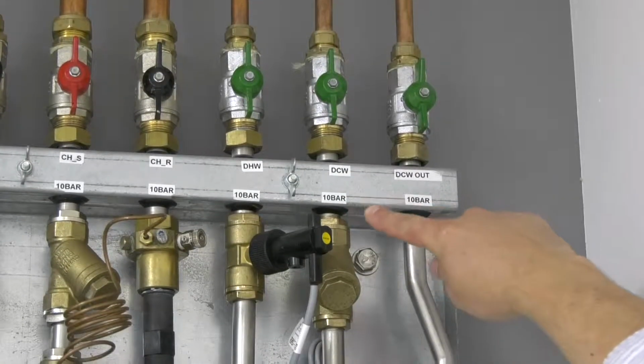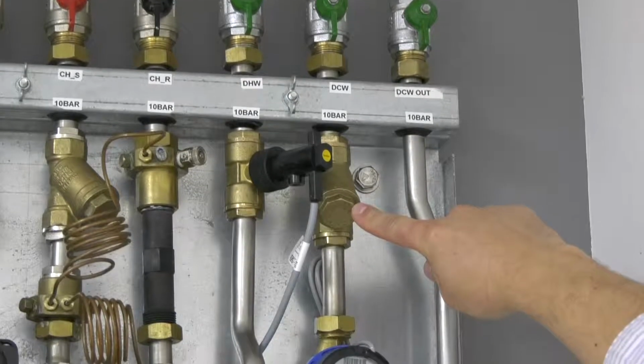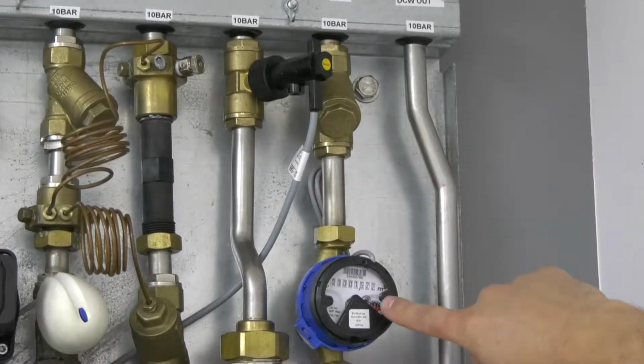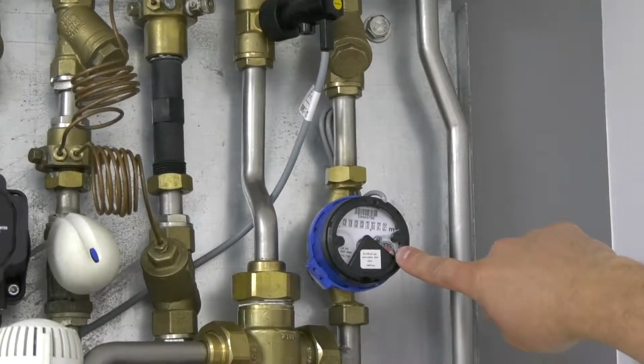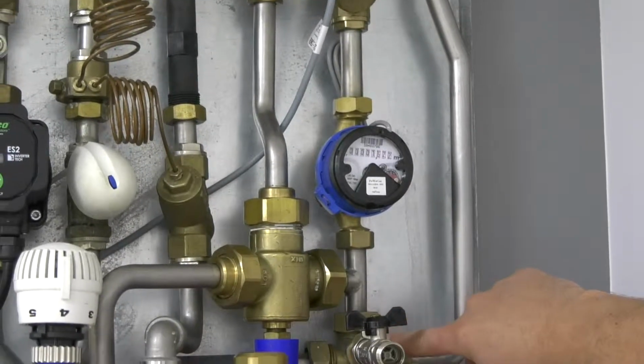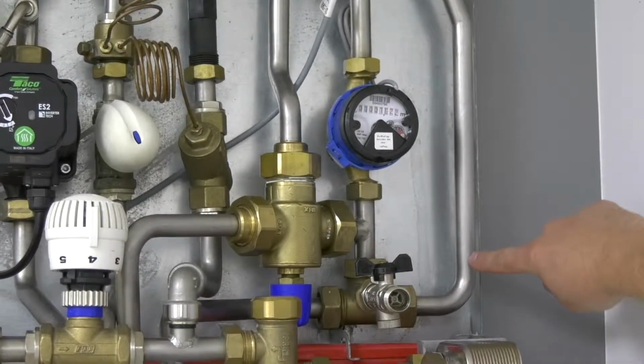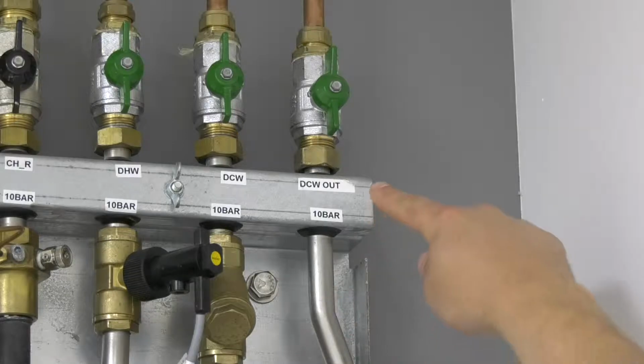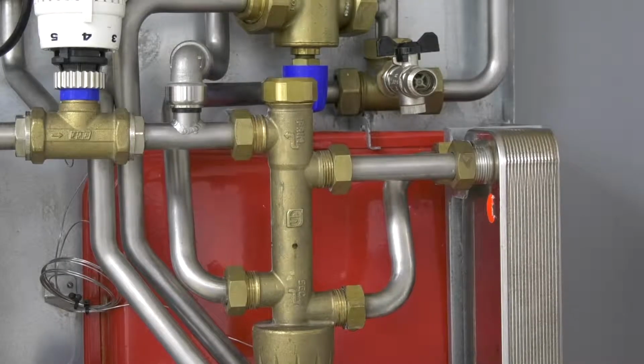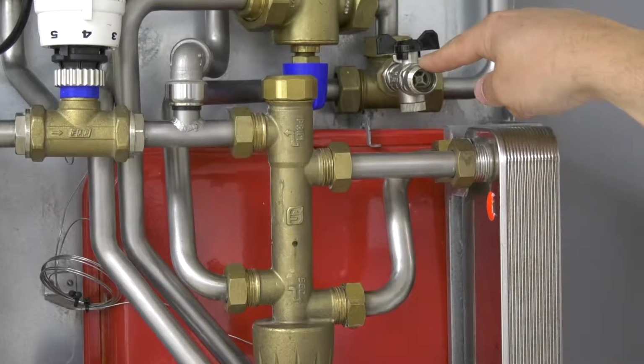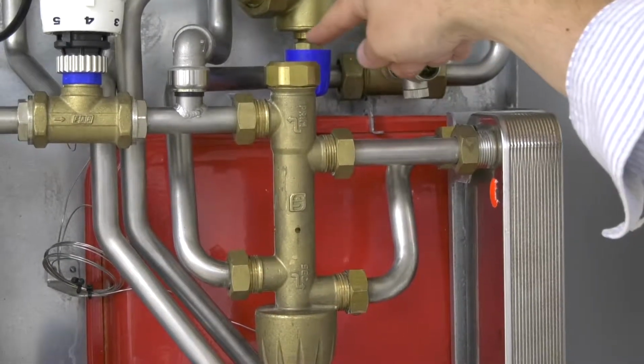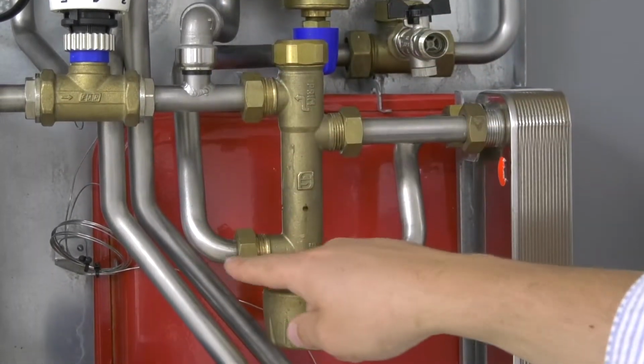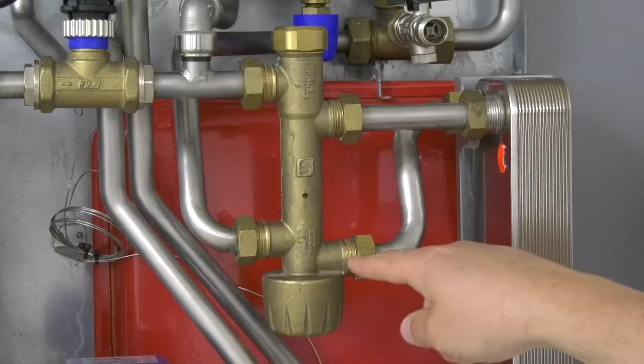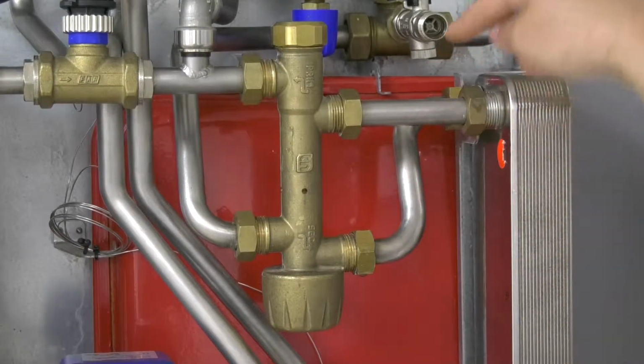Here you have the cold water inlet, the strainer to protect the system, and the water meter. Coming down to the T and back out then to the domestic cold water outlet. This is the bypass for your filling loop and the connection through the back down to the proportional valve and up to the hot water plate heat exchanger cold water inlet.